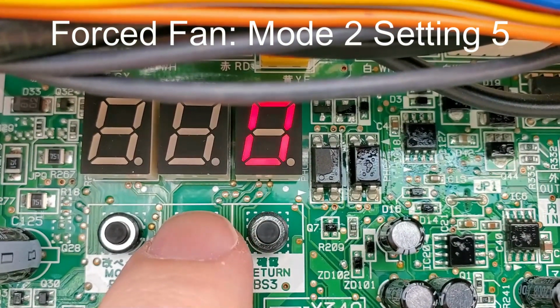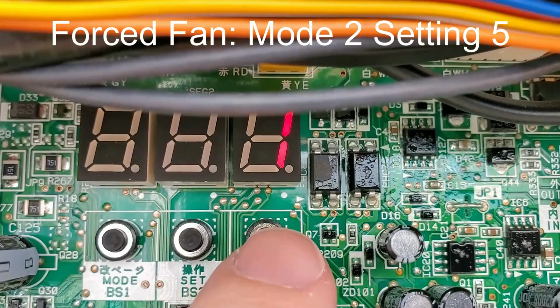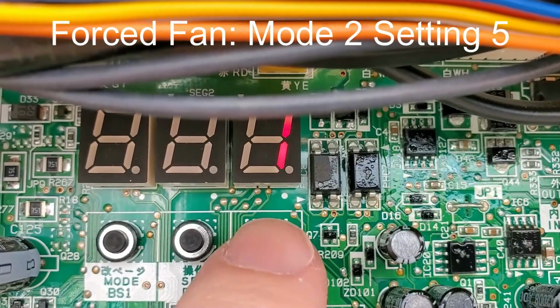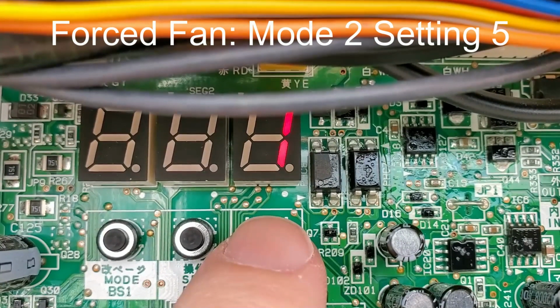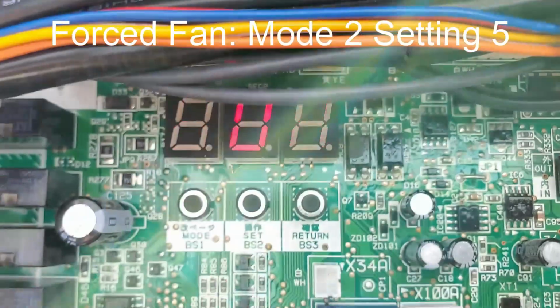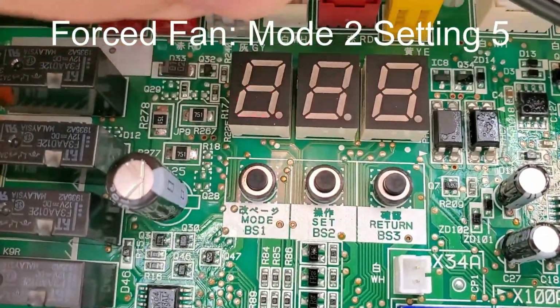It's going to flash a 0 on the screen. 0 on these newer boards means off. You're going to hit set 1 time, so it flashes a 1. That means on. I want to turn on forced fan operation, then hit return once. It goes from a flashing 1 to a solid 1. I've saved that setting and then hit return 1 more time. That activates the setting. It goes back to 2.00.